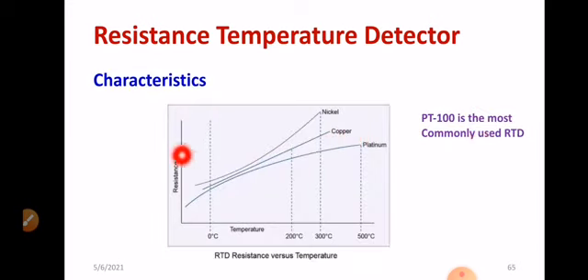This is a very important graph regarding RTD. The graph shows resistance versus temperature. In fact, you are measuring the resistance of that particular platinum wire. Then you will be plotting the curve of resistance with respect to temperature. This curve can be taken as a reference. You know that you can use platinum wire, copper and nickel. However, platinum gives a wide range of temperature measurement. For example, you are able to measure 500 degrees Celsius. This graph shows that platinum is better compared to the other two elements.